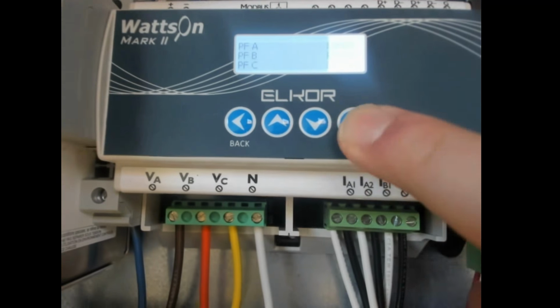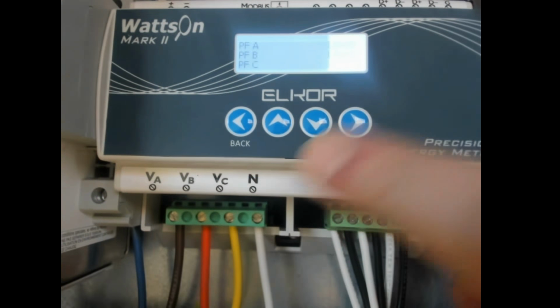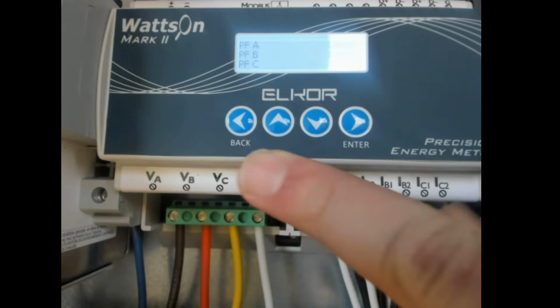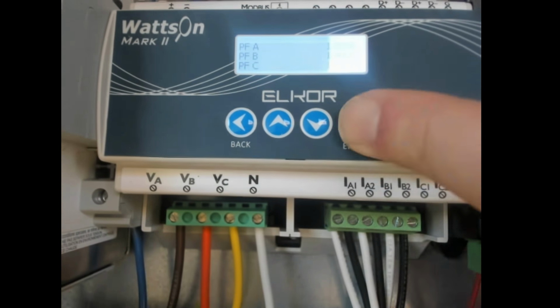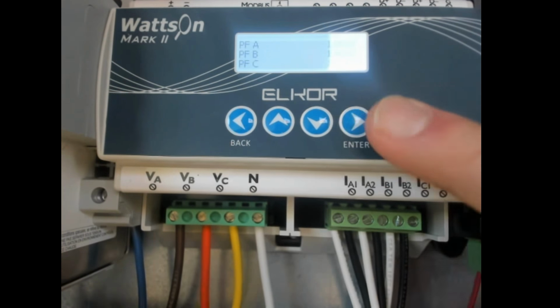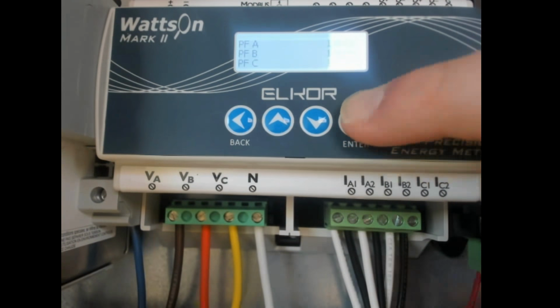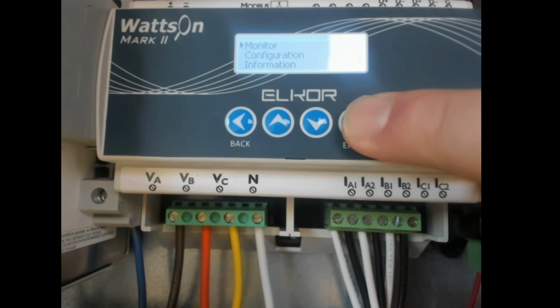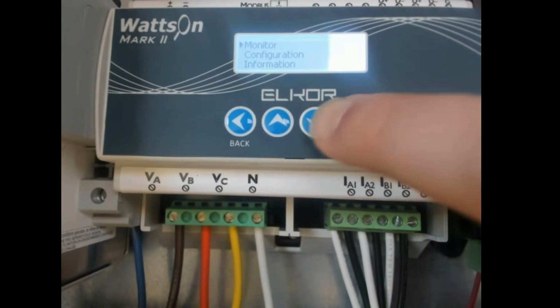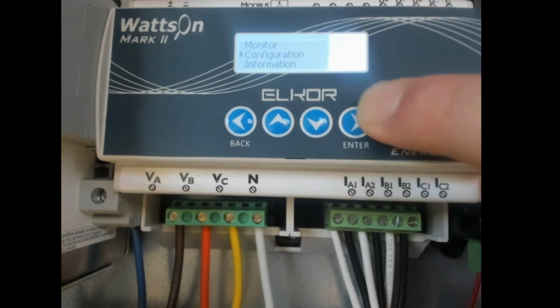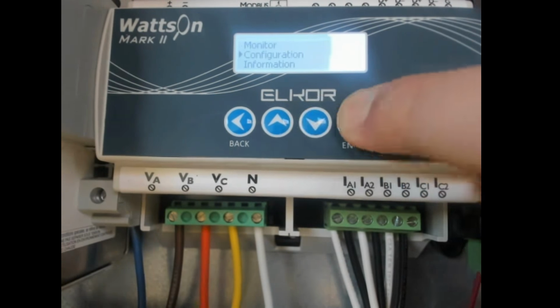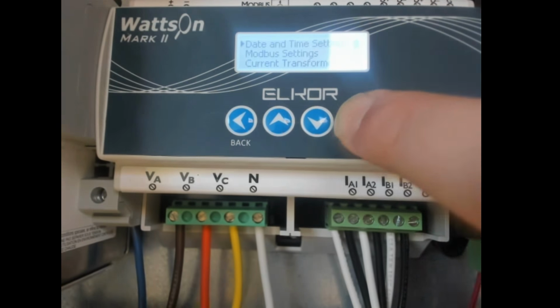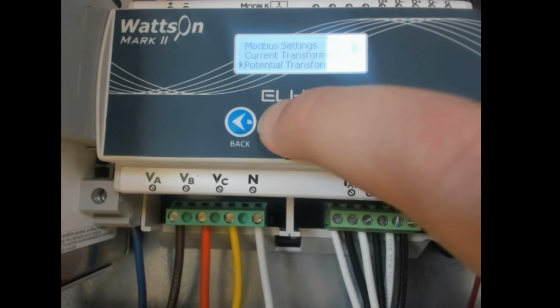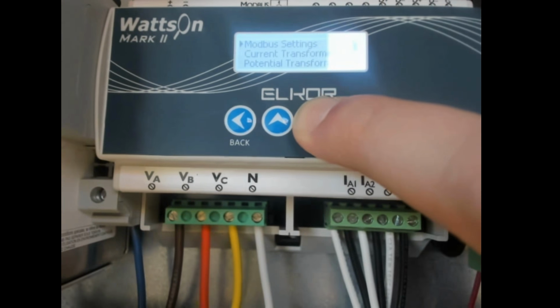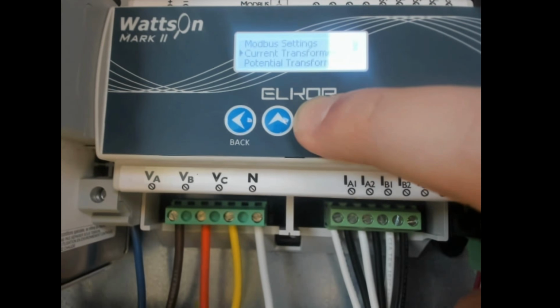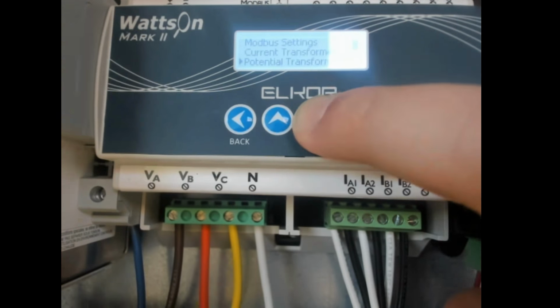If I press enter, you'll see the screen will line up, and we have the same directional buttons as the Veris pretty much. Whether Elkor took cues from Veris, it's definitely not vice versa. Veris came first with this local display. I don't care. It's really nice. So press enter, and that's going to go to the menu. The only menu we really care about is configuration. So scroll down to the configuration option, press the arrow key, and then we only really care about these three settings: Modbus settings, current settings for current transformers, and then potential transformers.